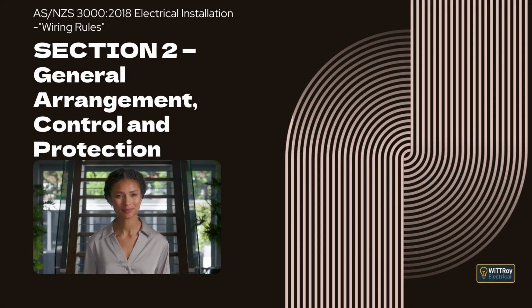Clause 2.3.3.5 Identification. A main switch must be clearly marked with the words main switch. It must stand out from the other devices on the switchboard so that anyone can identify it quickly in an emergency. If a switchboard has more than one main switch, each one must show which part of the installation it controls. If operating a main switch turns on or isolates an alternative supply, a notice must clearly show the location of the correct main switch for that supply.